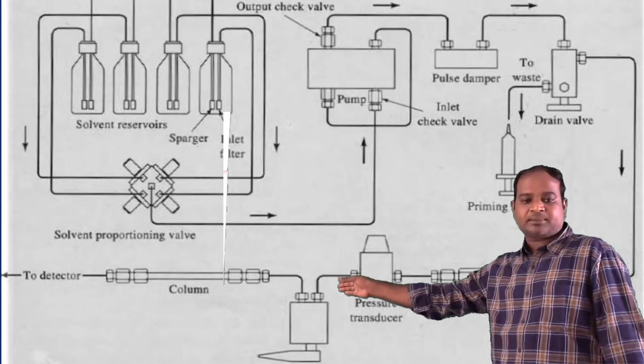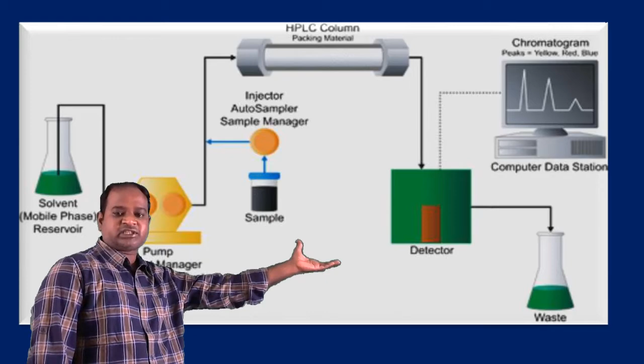This is another view of the HPLC column. See here the solvent, the mobile phase reservoir. Next, after the mobile phase, there is the pump, from where the solvent is pressurized to the main column, and from another way the sample is coming, and from here the solvent is coming. Both interact and go towards the main HPLC column, and finally it is detected at the detector, and the waste material comes out of the column.